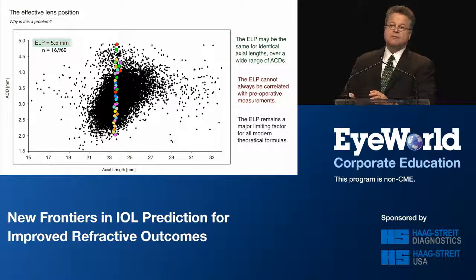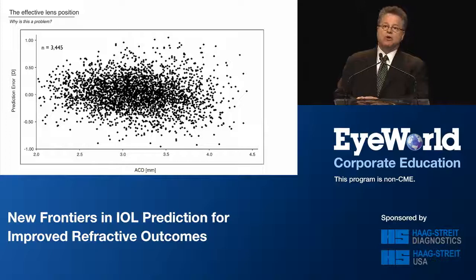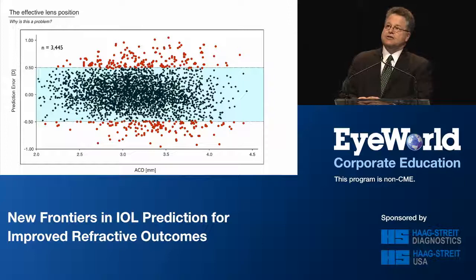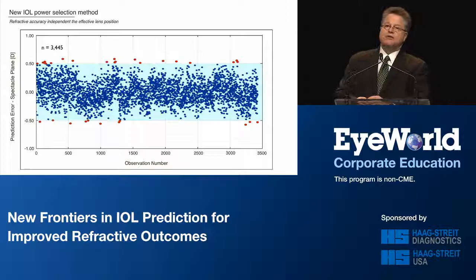Here's the database on the RBF method we're currently using. This is SRKT — these are all the cases outside half-diopter accuracy for about 3,400 cases. Here's that same database with the new method, and you can see the cases outside half-diopter accuracy are dramatically reduced.